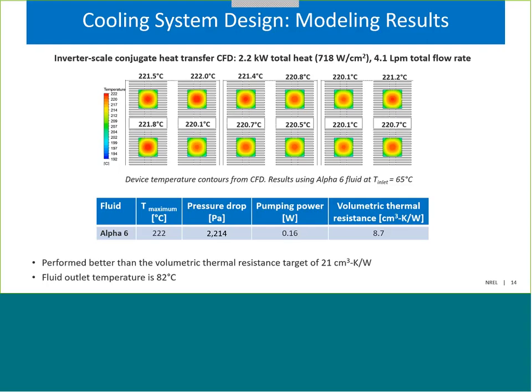And so we are exceeding the volumetric thermal resistance target of 21 centimeters cubed degrees per watt. In other words, lower resistance is better. Based on the fact that we have passed that resistance target, we estimate that a cooling system like this could potentially enable achieving the power density of 100 kilowatts per liter.